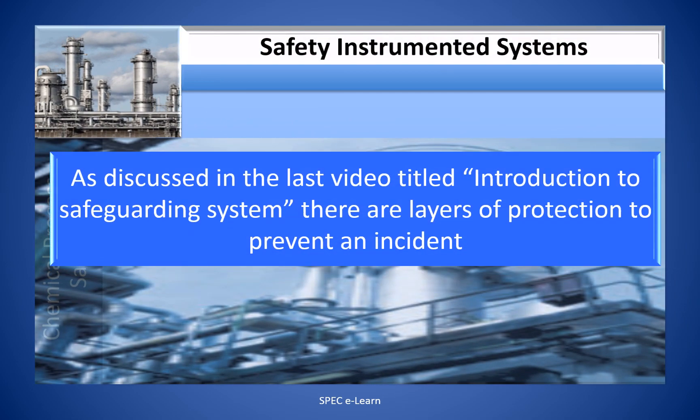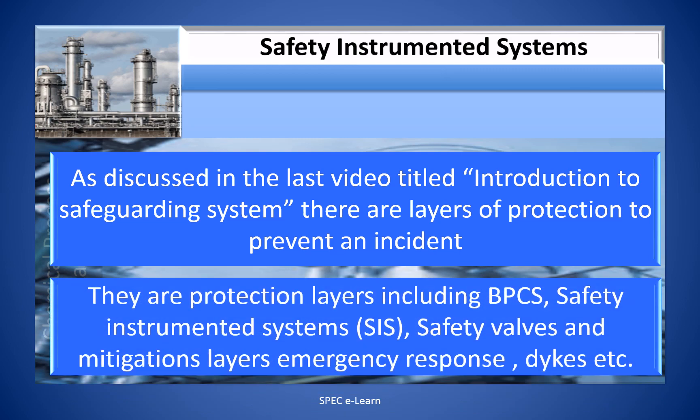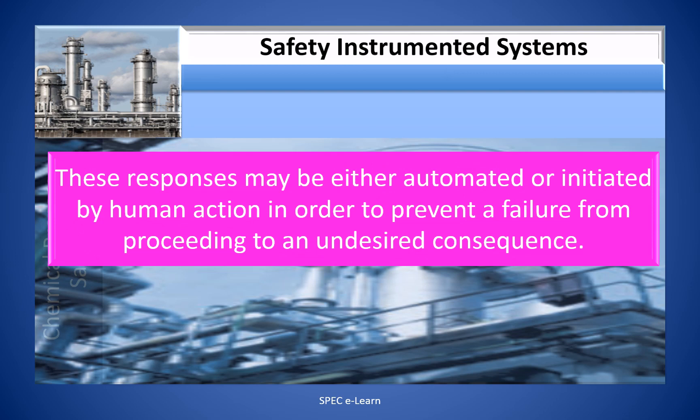As discussed in the last video titled Introduction to Safeguarding Systems, there are layers of protection to prevent an incident. These protection layers include the basic process control system, safety instrumented system, safety valves, and mitigation layers such as emergency response like dykes. These responses may be either automated or initiated by human action in order to prevent a failure from proceeding to an undesired consequence.